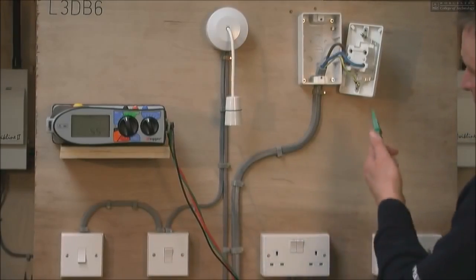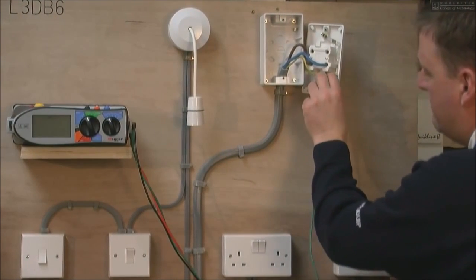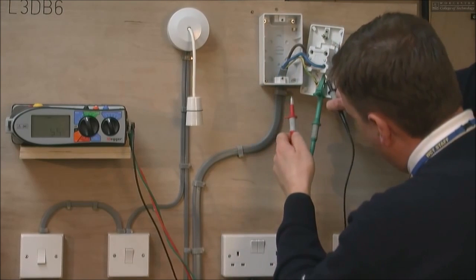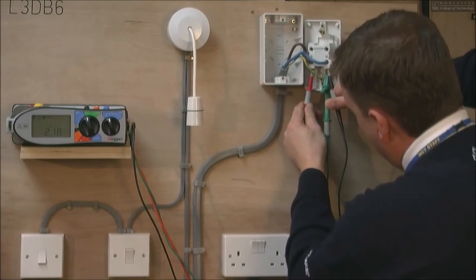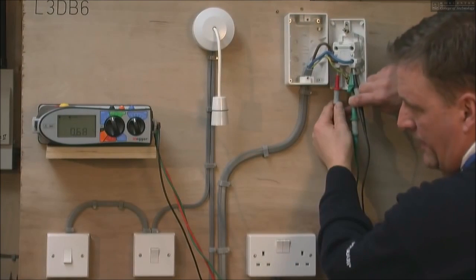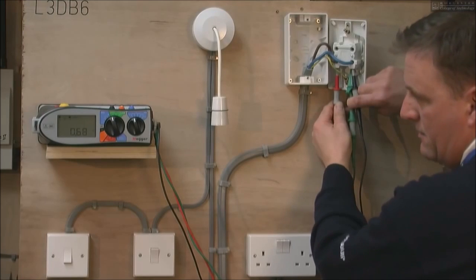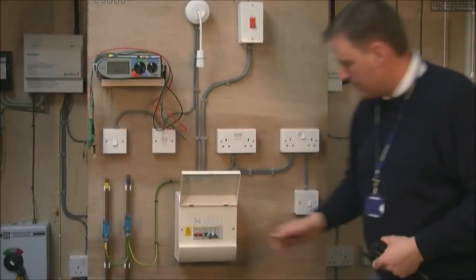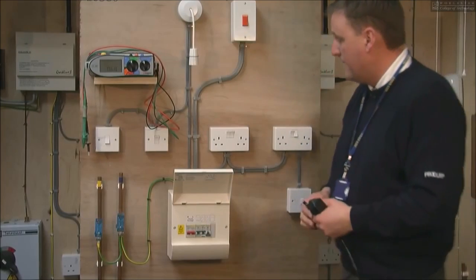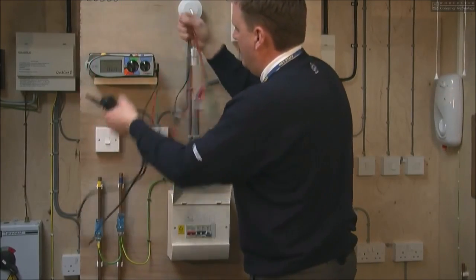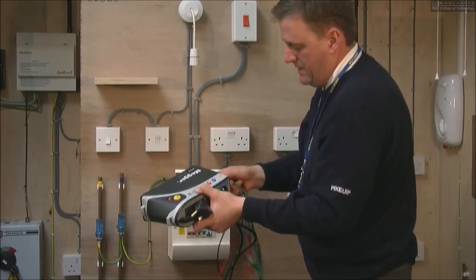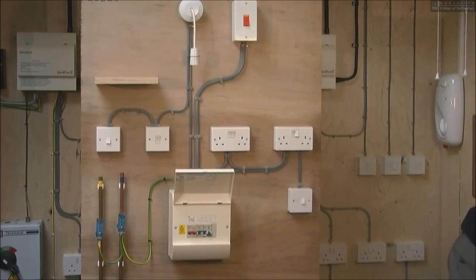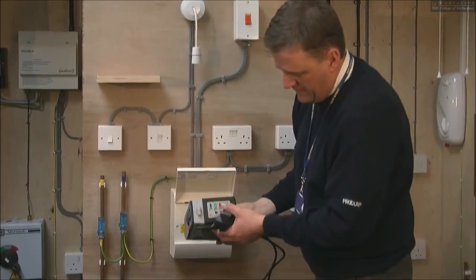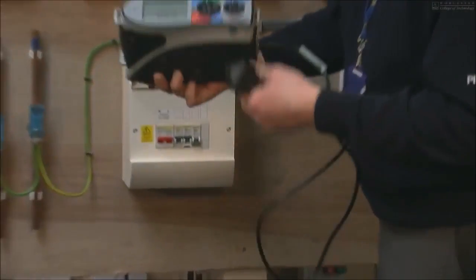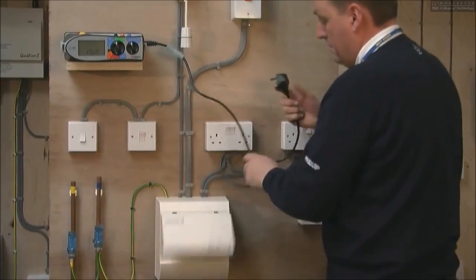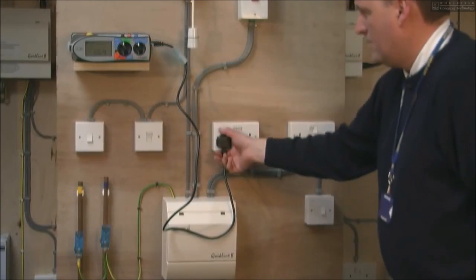We're going to do the Zs test on the cooker circuit. So onto the earth terminal, onto the neutral, and then onto the line conductor. And again, refer the readings to the latest regulations. The next circuit we're going to energise is the ring final, so we switch on the sockets. Obviously these leads aren't going to be appropriate, so we remove our test leads, like so. We then simply insert the plug-in tester. We do this for both the sockets.